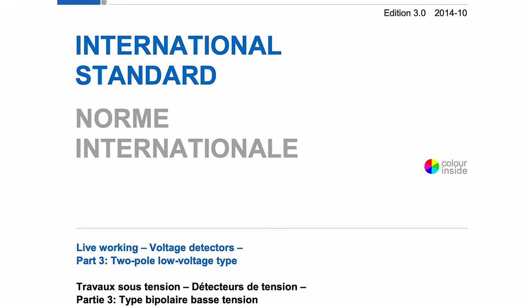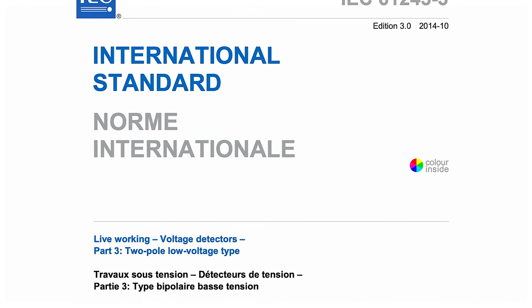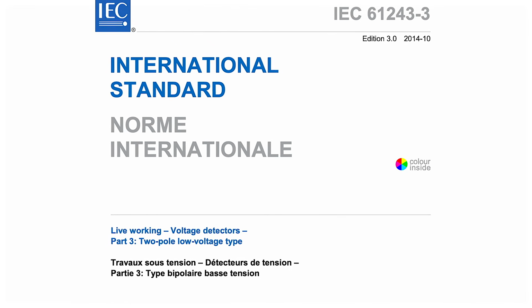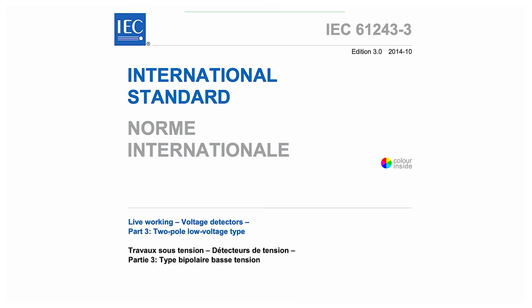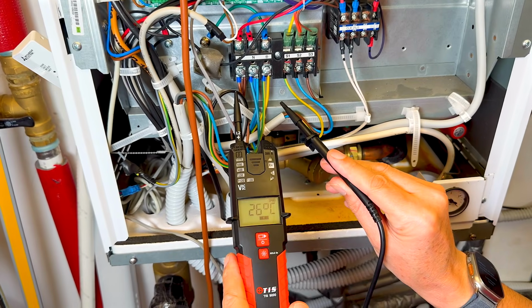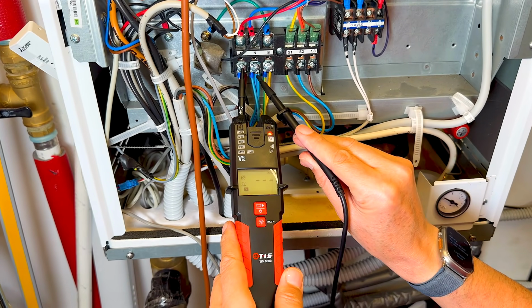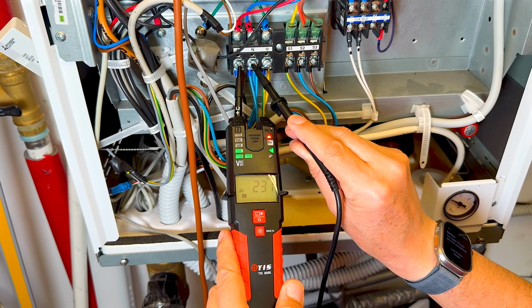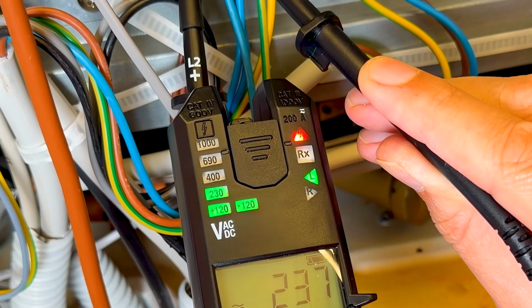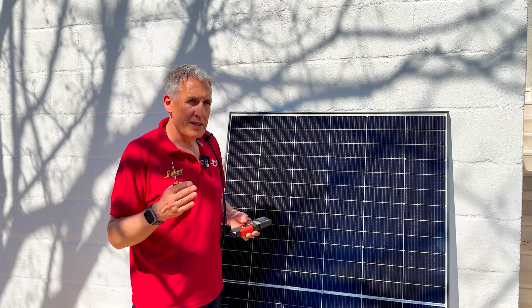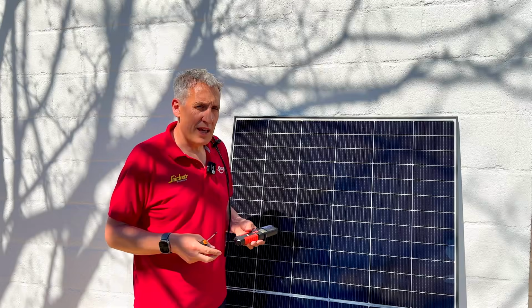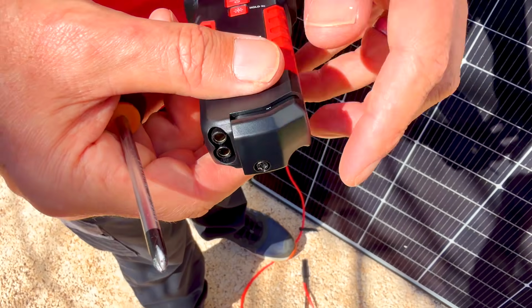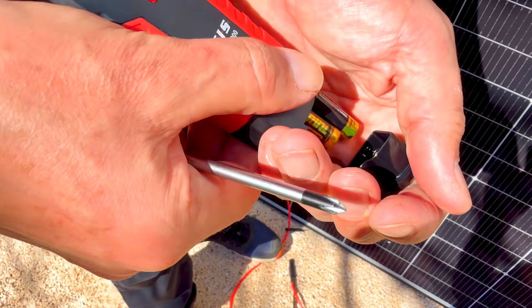And when you're proving dead, you need more than confidence, you need compliance. The TIS9000 complies with IEC 61243-3, the standard for voltage indicators used to confirm the absence of voltage. Crucially, it doesn't rely on you selecting the right function. Being a proved device, they also have an additional safety feature. If your battery has run flat, it must give an indication that voltage is present.